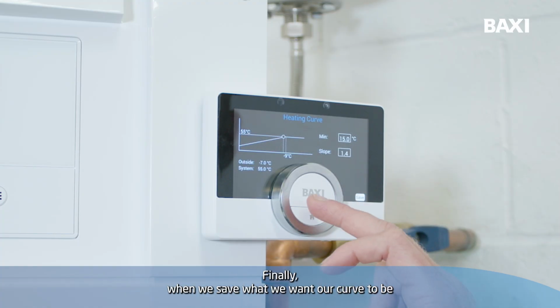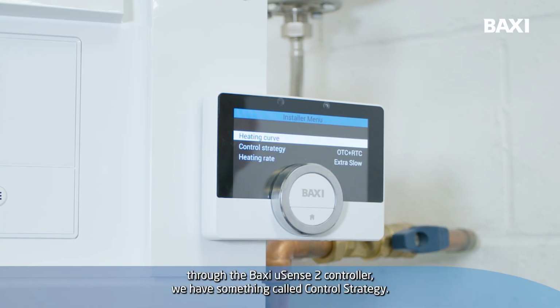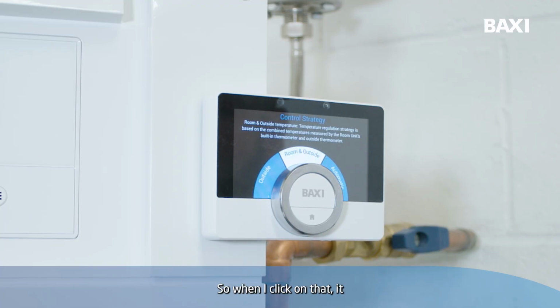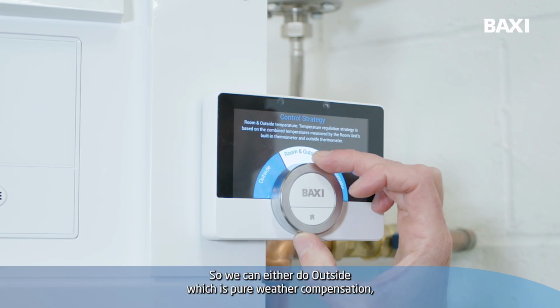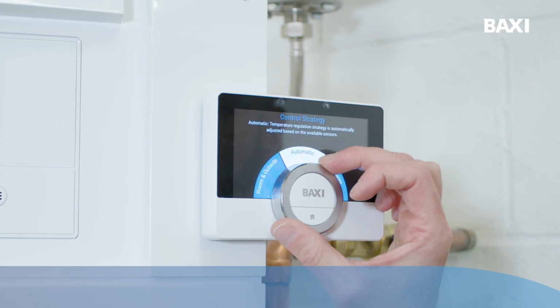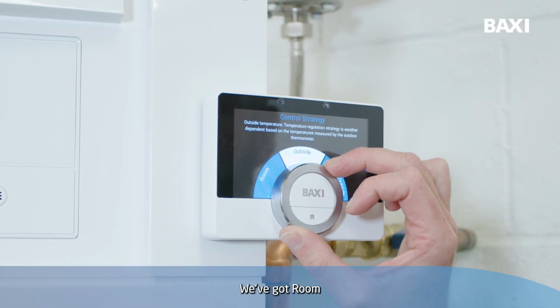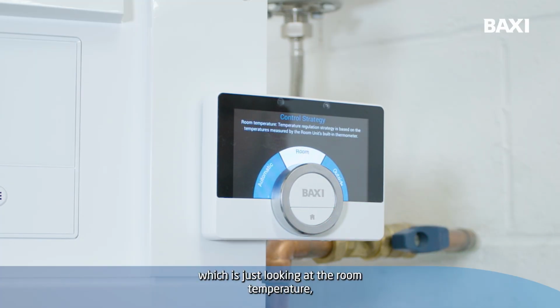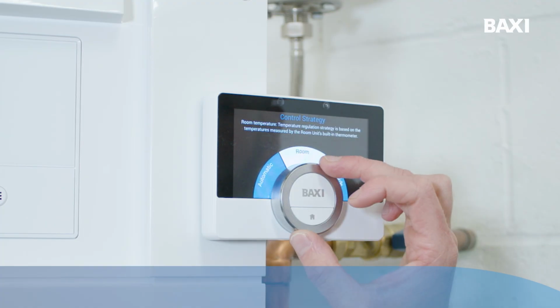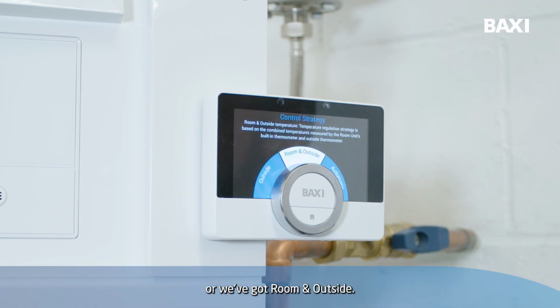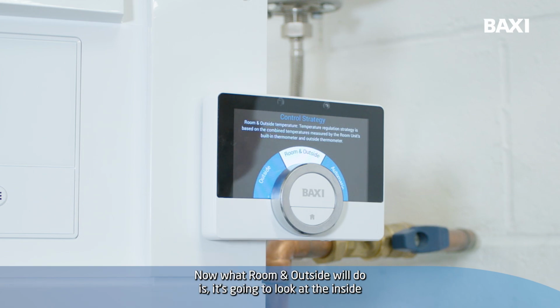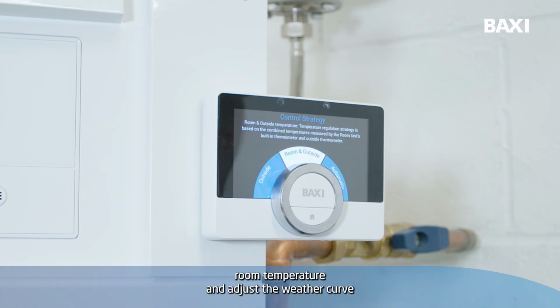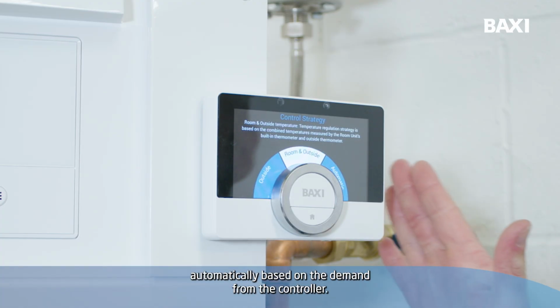Finally, when we save what we want our curve to be through the Baxi uSense 2 controller, we have something called control strategy. So when I click on that, it then asks me how we want to control that heating zone. So we can either do outside, which is pure weather compensation, which was there. We've got room, which is just looking at the room temperature. Or we've got room and outside. Now what room and outside will do is it's going to look at the inside room temperature and adjust the weather curve automatically based on the demand from the controller.